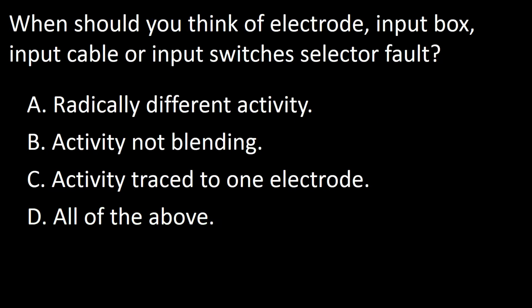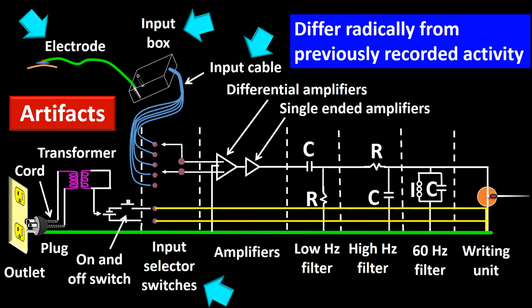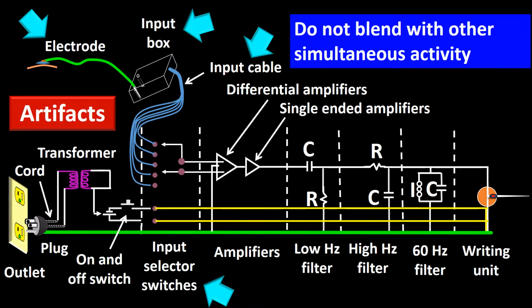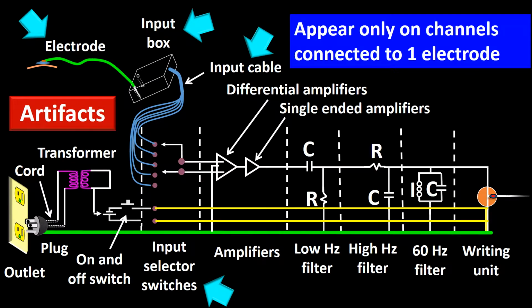When should you think of an electrode, input box, input cable, or input switch selector fault? A. When radically different activity is present. B. Activity not blending. C. Activity traced to one electrode. D. All of the above. You should think of a flaw in any of these elements when the activity present in the tracing becomes radically different from the previous activity, when the activity does not blend with other simultaneously occurring activity, and when the activity appears only in one channel.